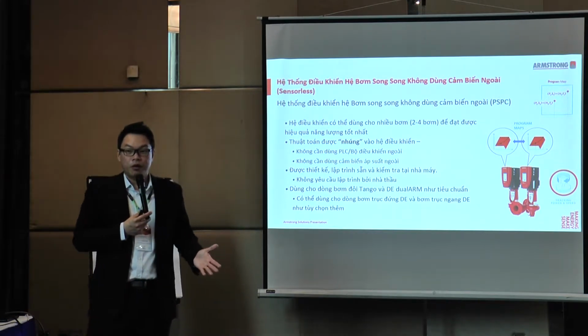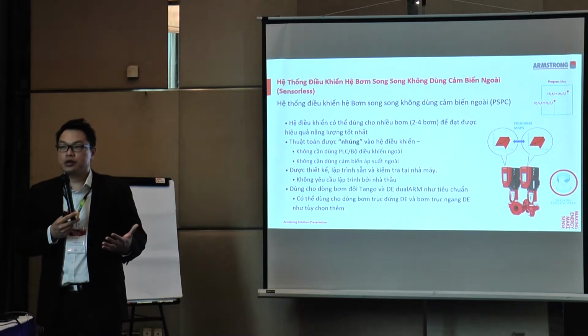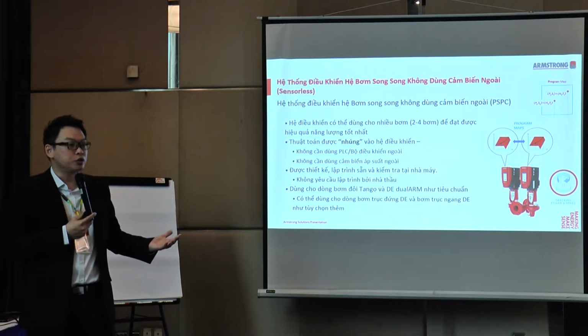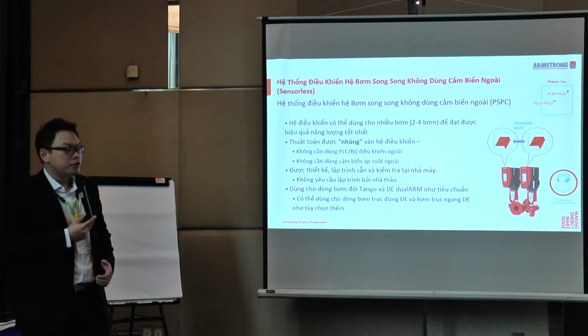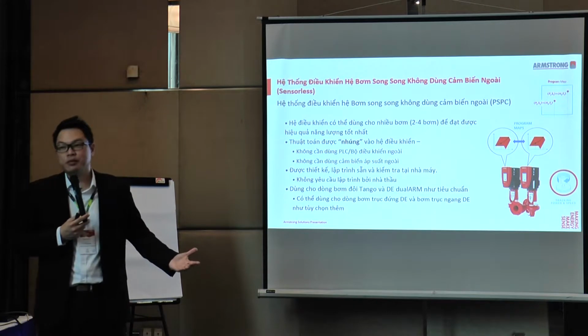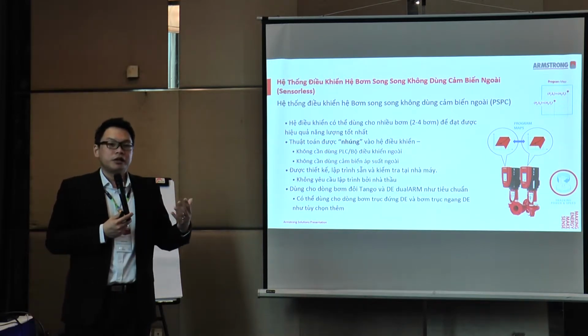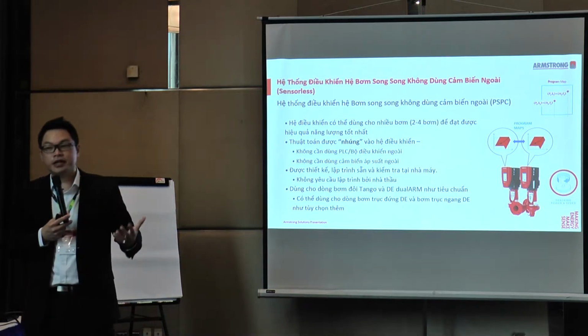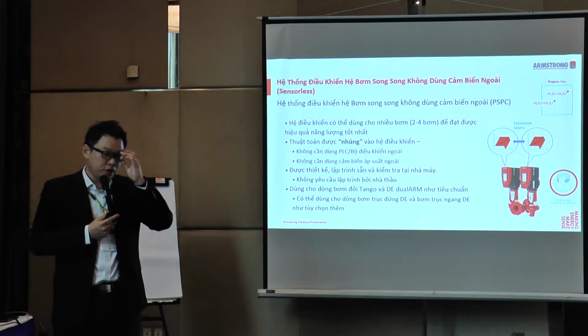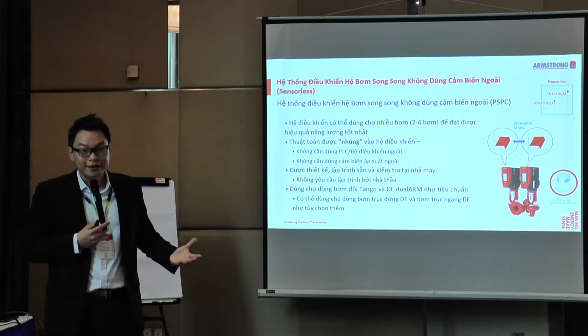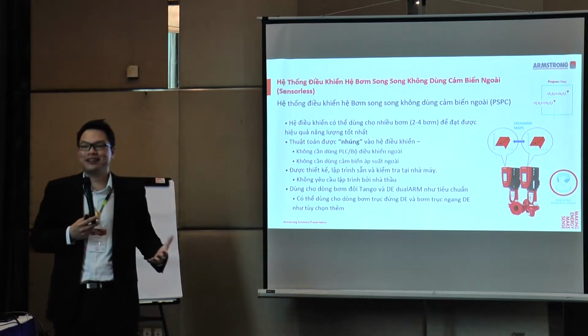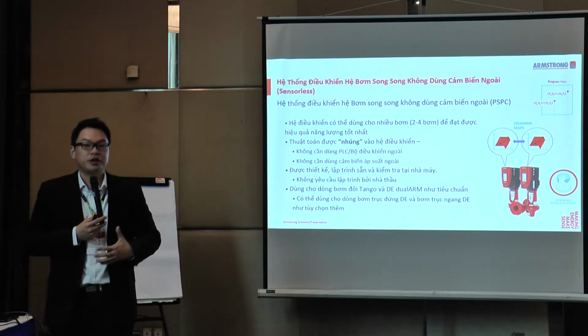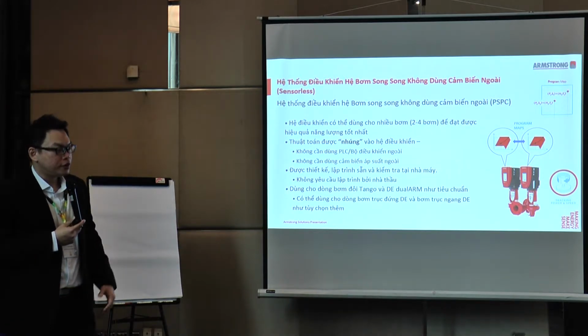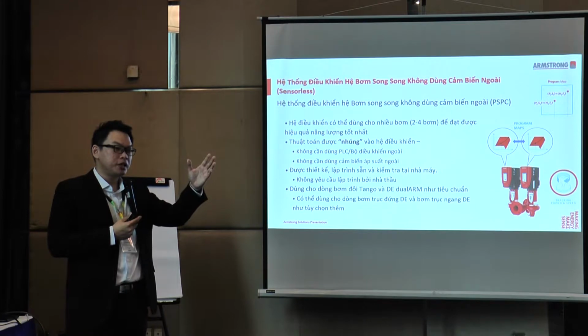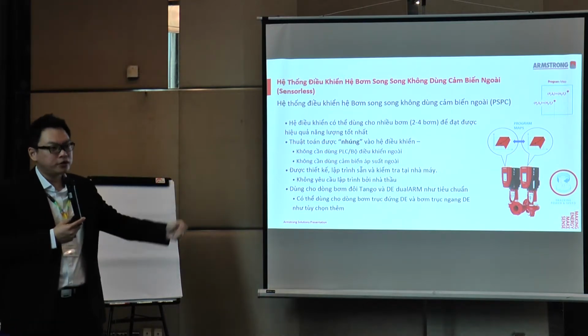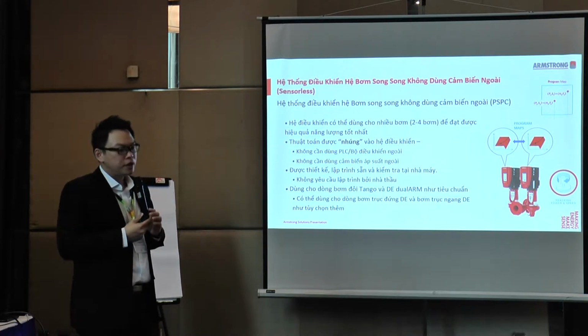are required. Alright? We know that DP sensors can be very tricky because to install them, there are always different rules. Maybe some of us put it at 2/3 of the way, some put it at the most remote load, or some just simply put it in a mechanical room. And of course, there's always the issue of maintaining the DP sensors. On some of our visits to site, some of the DP sensors are not working, right? The owners do acknowledge it's not working, but again, it's too troublesome to do a retrofit and replace the DP sensor. And of course, you need to consider the wiring from the DP sensors at wherever location you have placed them, all the way back to your VSD. So again, there's a lot of cost involved there.